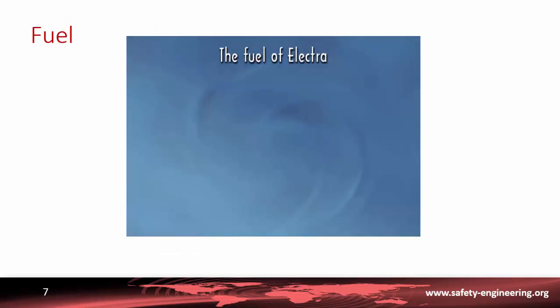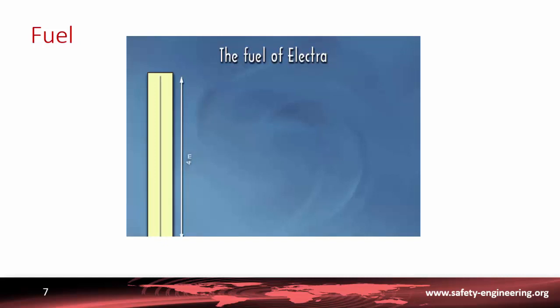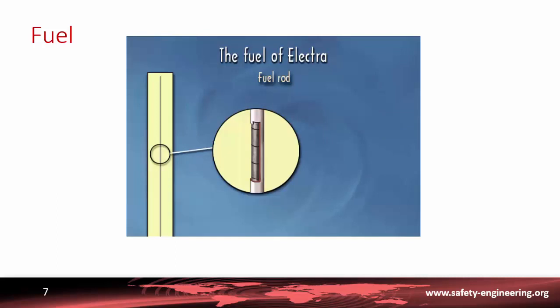The enriched uranium in which the energy is produced is contained in long thin tubes, some 4 meters in length and less than 1 centimeter in diameter — these are the fuel rods. Each rod contains a stack of cylindrical pellets made of uranium dioxide. The pellets are around 8 millimeters in diameter and 13.5 millimeters high, with around 300 in each rod. The metal tube forming the outer shell of the rod, referred to as the cladding, is made of an alloy of zirconium.